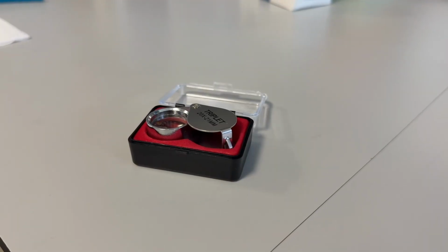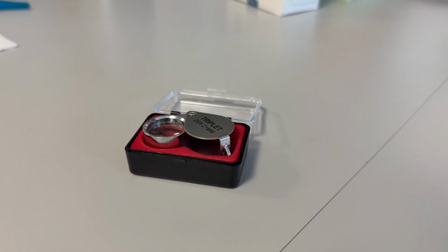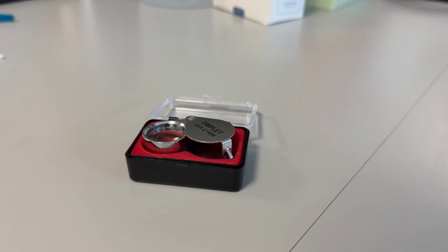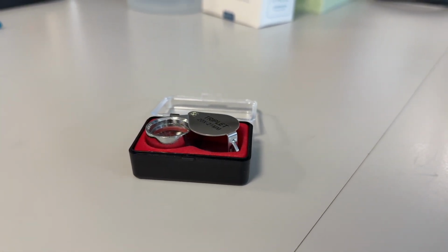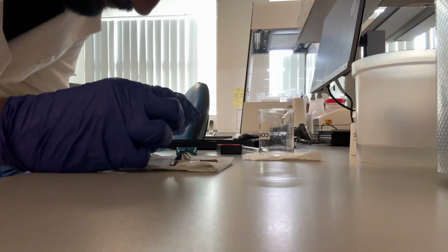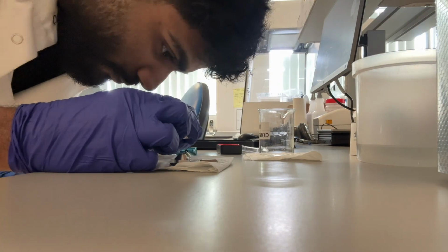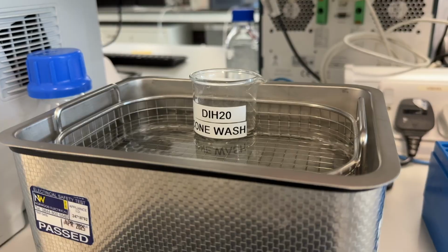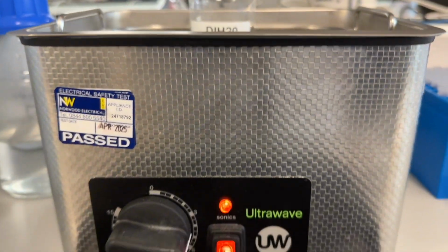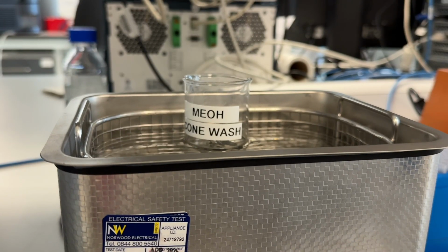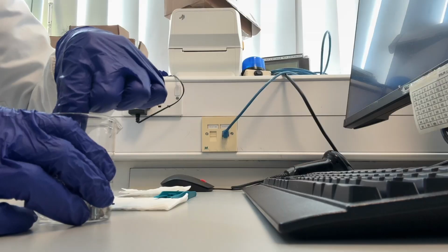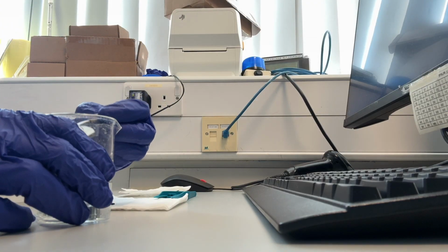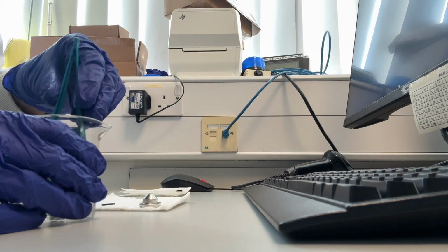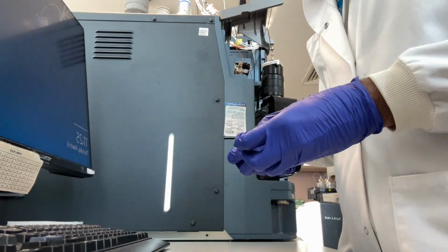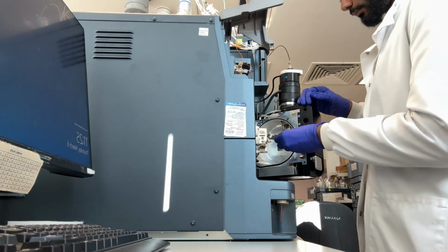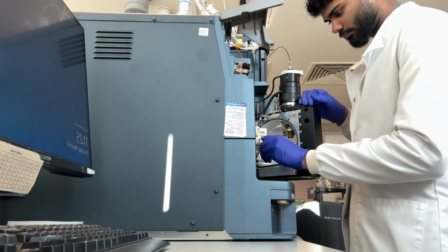After the first wash is done, I'll give the cone an inspection with this eyepiece to check for any imperfections in the cone, as it is essential that there is no damage to the cone, as this affects the assay quite badly due to the electrospray not being performed as it should. I then put the cone for a wash with deionized water for 5 minutes, and then methanol for another 5 minutes. After the wash is done, I have to let it dry. Now that it's dry, I'll reassemble the module, making sure the ring is placed on tightly, and place it back into the mass spec.